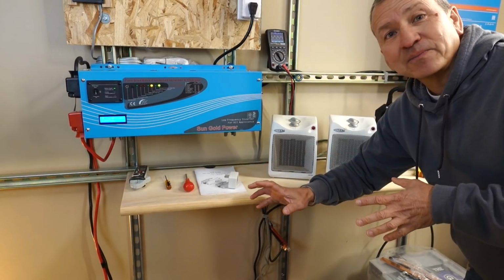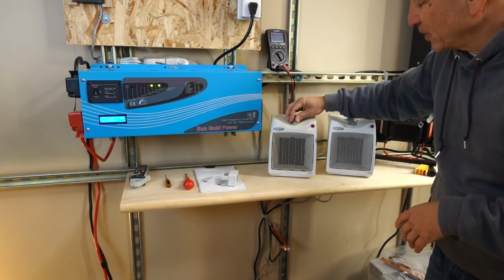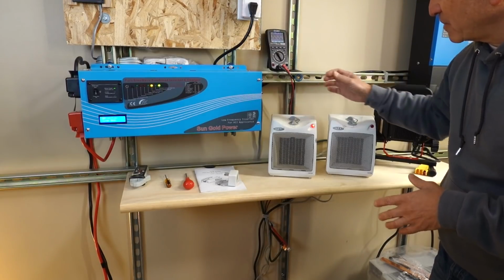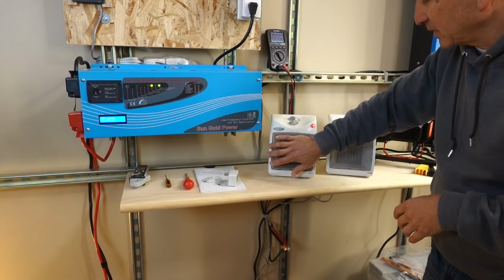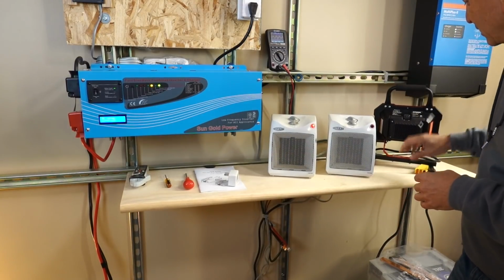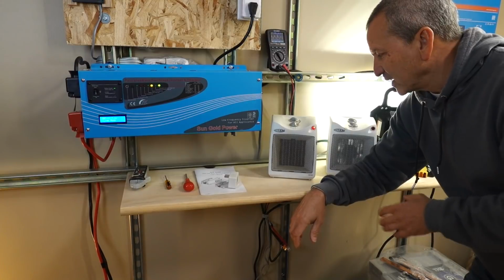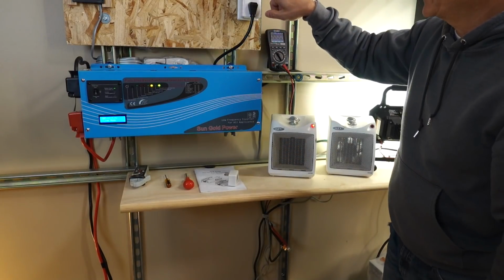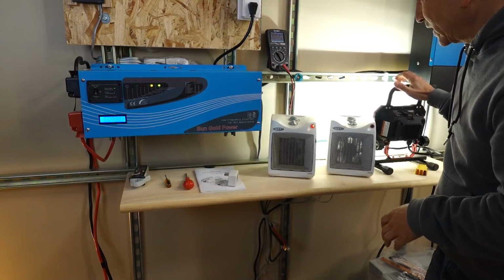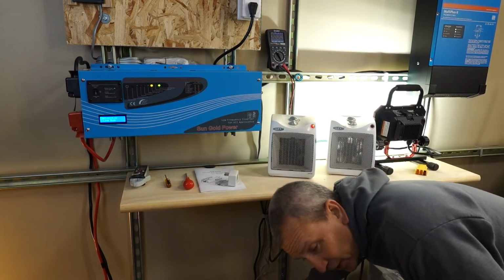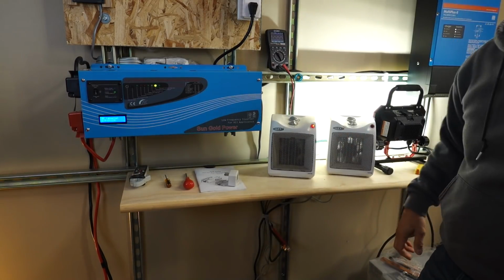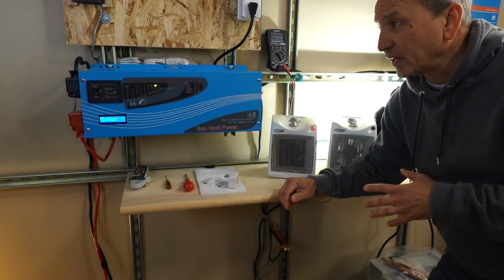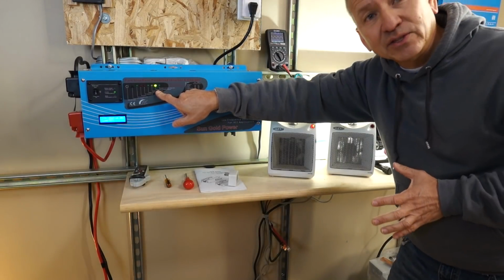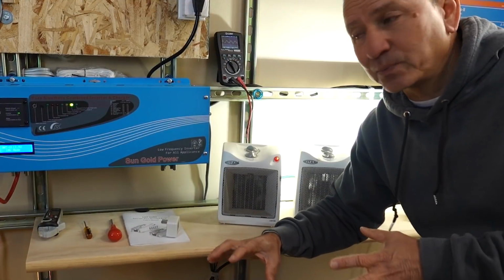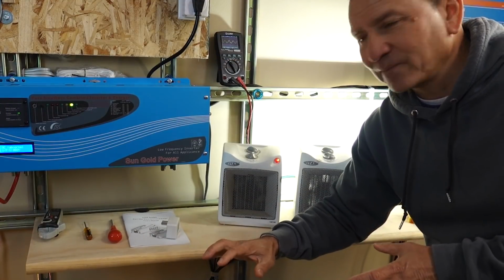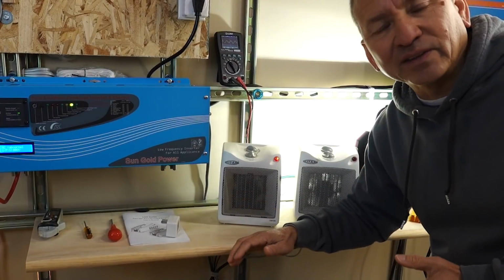So now we've got AC power restored, switched back. I'm going to turn on my heater, get some heat, and we'll turn on a light. All right, so we've got some stuff running, drawing about 550 watts. I'm going to go ahead and switch the AC power off now. Here we go, off. Nothing changed, everything is still running, but the inverter switched back over into inverter mode. So that switch is pretty quick. It's like 8 milliseconds, and it's not even noticeable for this equipment that's hooked up to it.